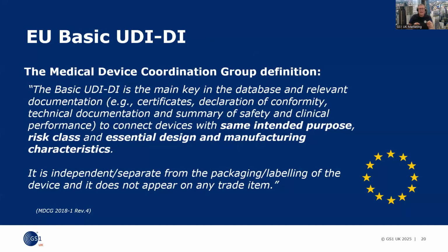It's the main key in a database and relevant documentation to connect devices with the same intended purpose, risk class, and essential design and manufacturing characteristics. Remembering that it's independent from the packaging of the device and it does not appear on the device or its packaging.